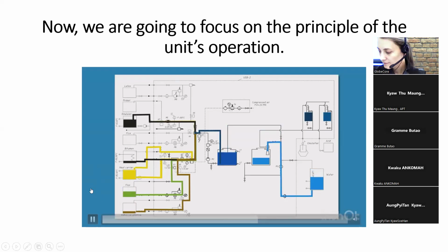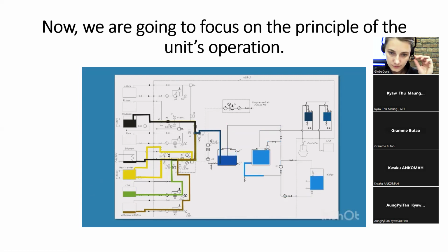When the water phase is pumped into the consumption tank and the liquid rises to the top level sensor, an audible alarm goes off as well, warning the operator that the valves are switching to circulation of liquid in the preparation tank or to pumping a new volume of water for preparation of water phase. If, again, after a preset time interval, the liquid level has not resumed the point below the top level, then the unit automatically shuts down to prevent alarm conditions.